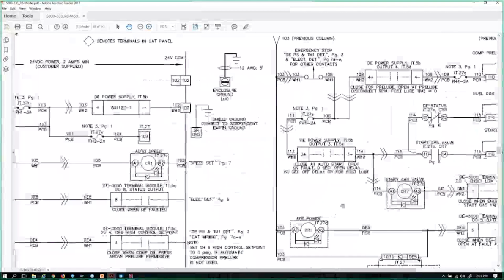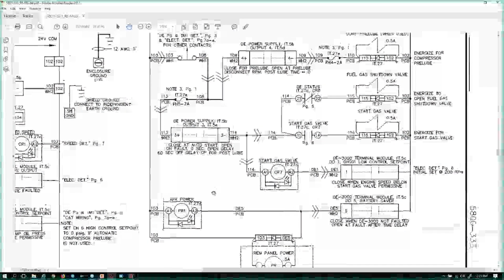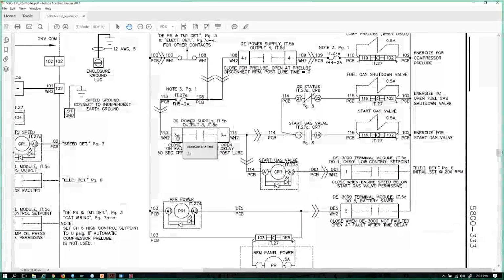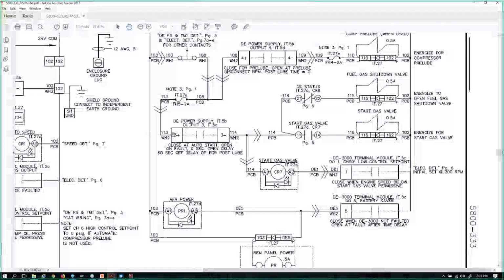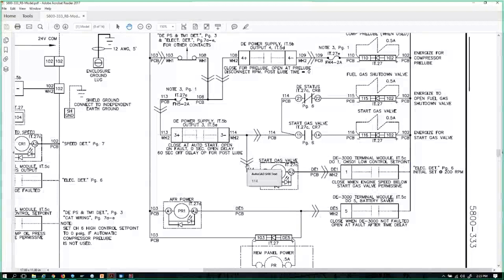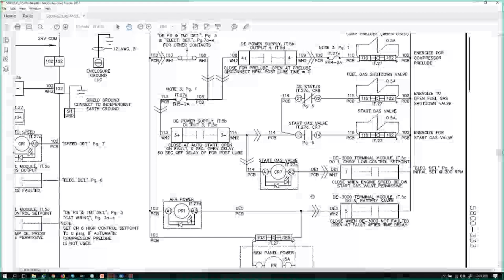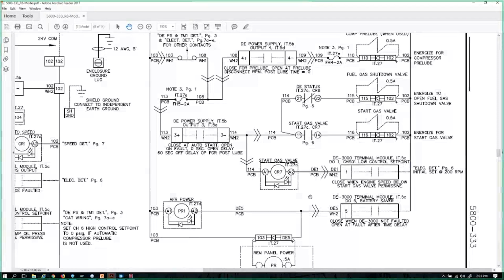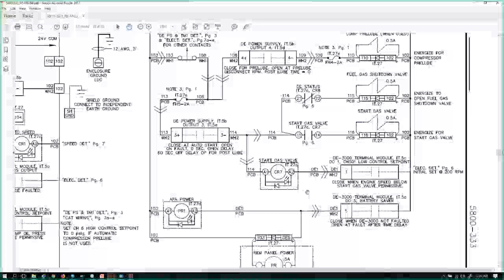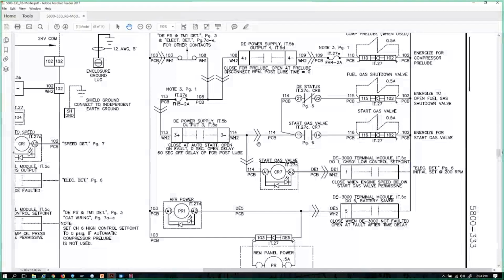and this is just a generic DE-3000 flex panel, I can see a circuit where I'm using output module 3 on the power supply board to supply, through an ESD switch, 24 volt power. So I can say on this one, closed at auto start, and we'll just stop right there. So when it goes into auto start, this closes and puts 24 volts on this circuit. Sorry for all these little pop-ups. I'll try to keep my mouse from allowing that to happen. I'm providing 24 volts to the circuit 114.